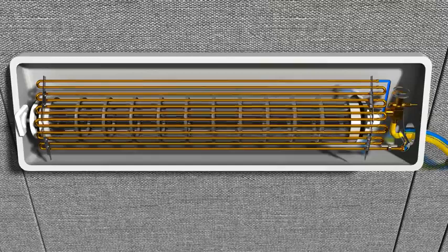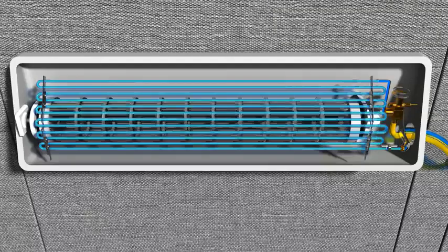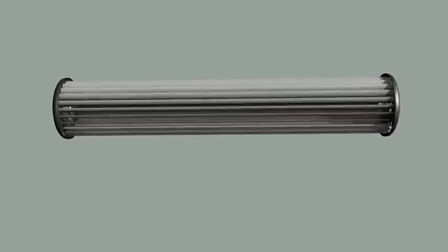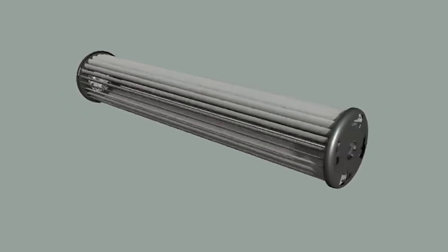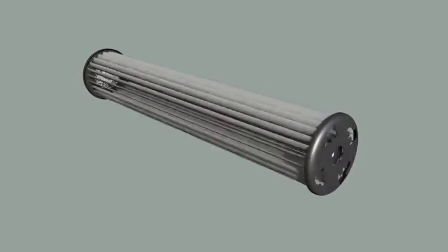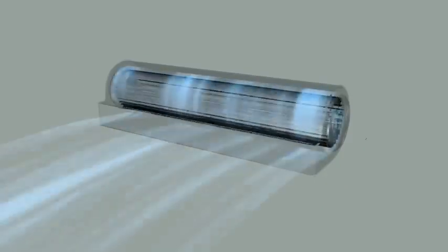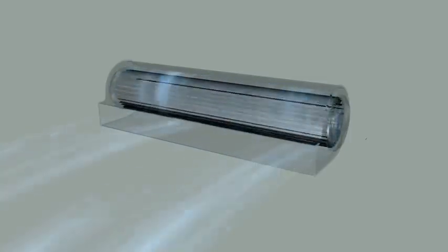A refrigerant passes through the pipes of an evaporator and takes away heat in this process. As the fan underneath starts to operate, warm air in the room is sent to the evaporator and cooled air is emitted. The fan used in the indoor unit of an air conditioner is shaped as a cylinder rather than the more familiar version of a propeller. Such a type of fan is called an impeller. As wall-mounted air conditioners cannot take up large space, the impeller type of fan is used instead of the propeller type.